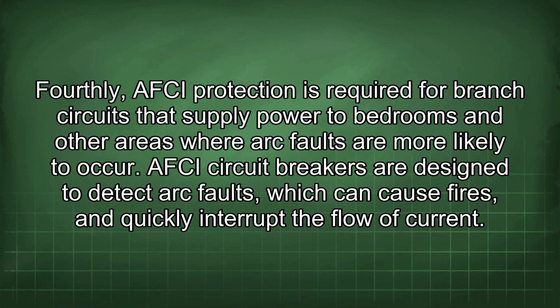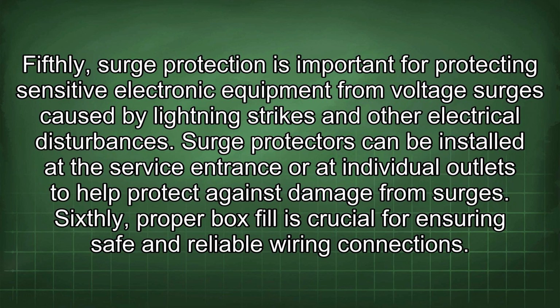Fourthly, AFCI protection is required for branch circuits that supply power to bedrooms and other areas where arc faults are more likely to occur. AFCI circuit breakers are designed to detect arc faults, which can cause fires, and quickly interrupt the flow of current. Fifthly, surge protection is important for protecting sensitive electronic equipment from voltage surges caused by lightning strikes and other electrical disturbances. Surge protectors can be installed at the service entrance or at individual outlets to help protect against damage from surges.